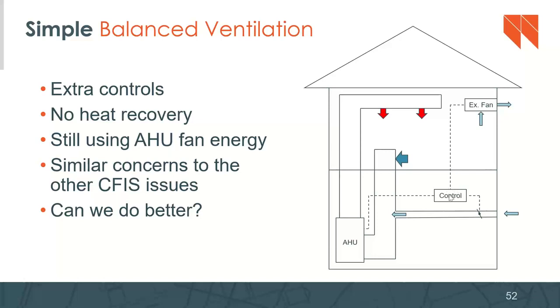central fan integrated system controller has the ability to not only open the damper on your outside air duct, but it can also run the air handler, and it can also tell the bath fan to exhaust. And so we're counting this as a balanced system. There's no heat recovery, but it is balanced. We're keeping that pressure difference across the enclosure neutral, i.e. balanced. It's got similar concerns as the other central fan integrated systems, that supply only stuff.